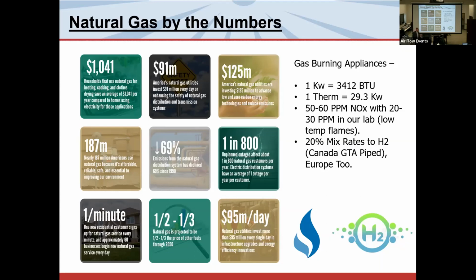And I can tell you what's already happening. The greater Toronto area, the GTA, has already provided all of their piping in that area that allows a 20% mix of hydrogen into the natural gas. We in Europe are already being told we have to make heaters that burn 20% hydrogen and 80% natural gas. So they're blending. Now, this is really a big thing. I don't know when the infrastructure will be solely hydrogen. That's going to be years and years away, and it's very difficult to combust. But mixing natural gas with it is kind of the best of both worlds. We can do that now, and we are. The Europeans have a bigger problem. They're trying to get away from natural gas. Why? Because most of it comes from Russia, right?